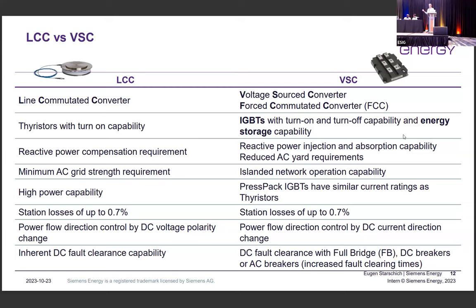what is required by the DC grid? If you have DC grid requirements, you will need to use either one DC breaker technology or the other one. One is called mechanical or hybrid DC breakers, or solid state DC breakers, completely based on semiconductor technology. So one or the other. Most of the breakers available on the market are hybrid DC breakers, which have fault clearing times in milliseconds, which might not be sufficient from the DC grid point of view. So if we really want to apply DC breakers for DC grids, we need to first define how we want to operate the DC grids and what the resulting fault clearing time is, and then we can design or introduce the specific DC breakers for this purpose.